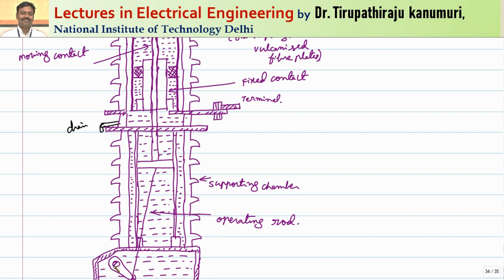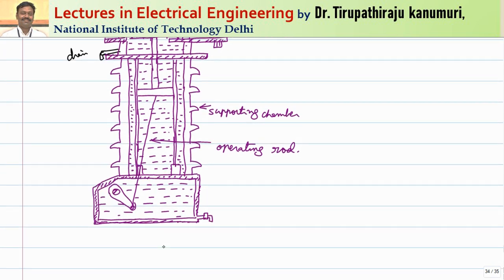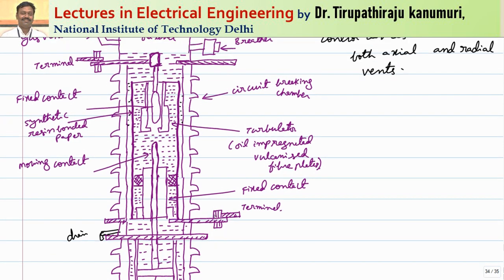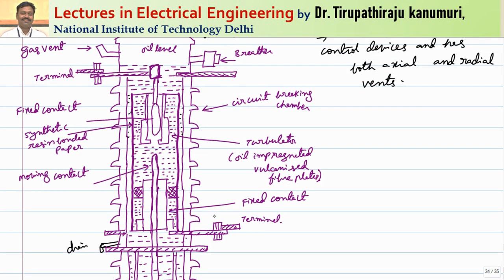On the lower side there is a third chamber called the supporting chamber. The supporting chamber is completely isolated from the upper chamber and is also filled with oil. Here the purpose of the oil is only to provide insulation to the moving parts — the operating rod, lever, and other metal components. Since this oil is not linked to the upper chamber, it does not need to be replaced frequently. A drain plug is provided for both the supporting chamber and the circuit breaking chamber.